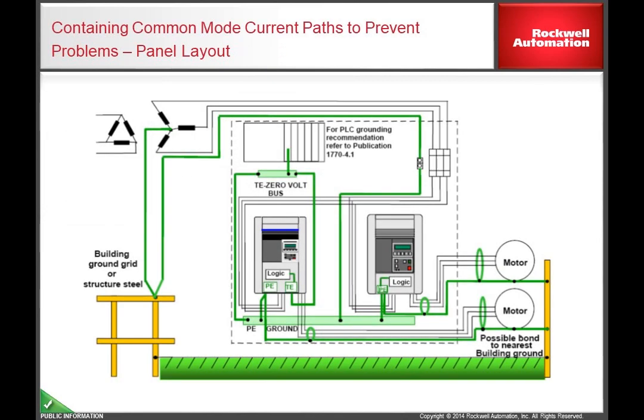Drives, in general, are a significant source of noise to any electrical system. In other videos in this series, we discuss what common mode current is and how to configure the drive to best contain common mode current. Those videos are designed to help understand the power jumpers within the drive and how this can help reduce noise-related issues in your electrical system. Taking these steps will greatly reduce the effects of common mode current in a facility by routing the current back to the source. Please see the description for links to these videos.